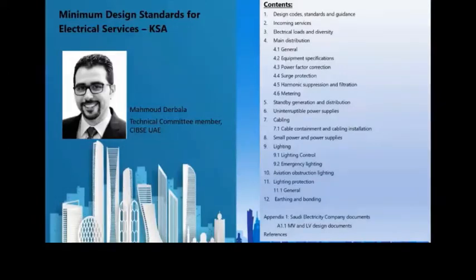While the local means of load calculation should be used to establish the total connected load, the designer shall endeavor to incorporate design solutions to minimize the operational load and reduce the overall energy consumption, considering the demand factors and coincident factor, which are listed in DPS01 as well. The coincident factor is the inverse of the diversity factor; they call it that in SEC documents.